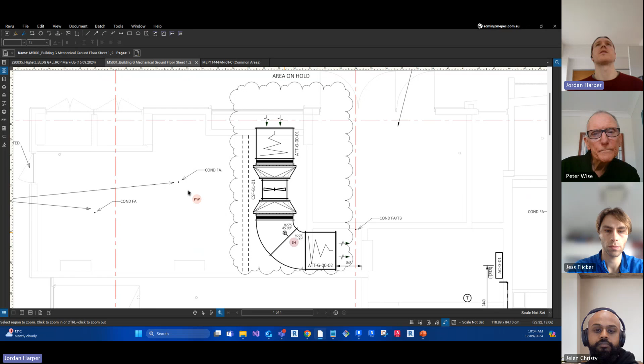Well, that's something you could do, but as you can see, that attenuator is right on the bend. If you look at the recommendations, they say if you could have a straight piece of duct after the bend to the attenuator, that would help it do its job a lot better, but you haven't got space for that. So it's a difficult one - it would certainly need to be looked at carefully, probably by someone who is a specialist in acoustics.